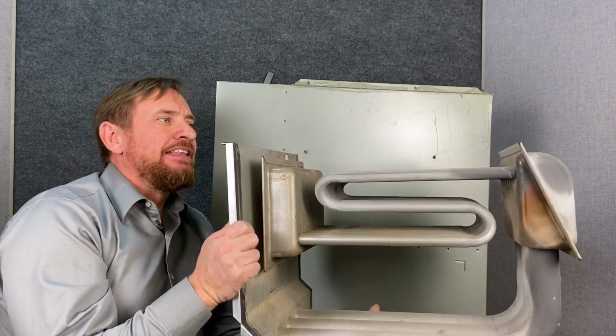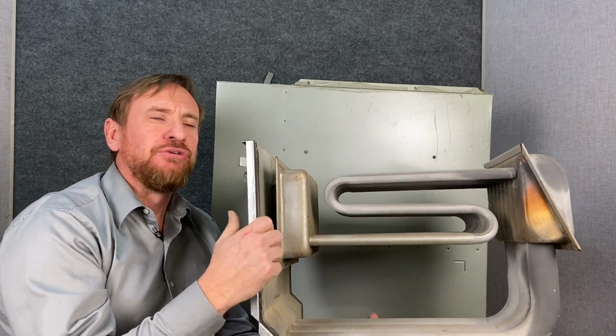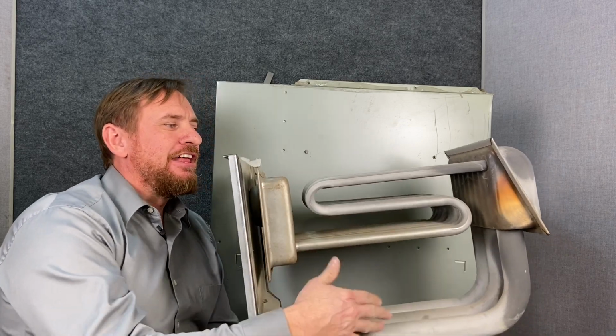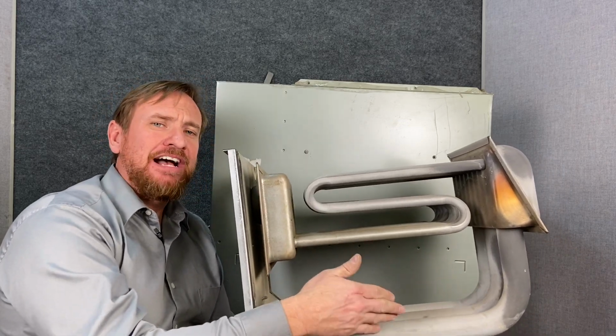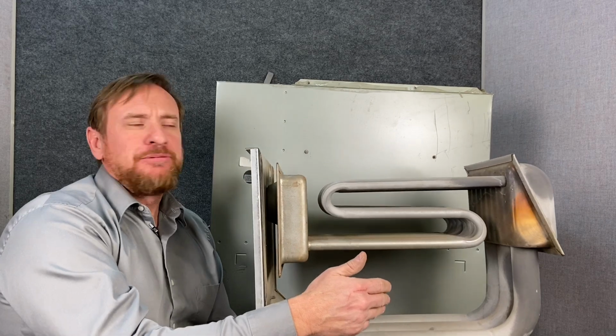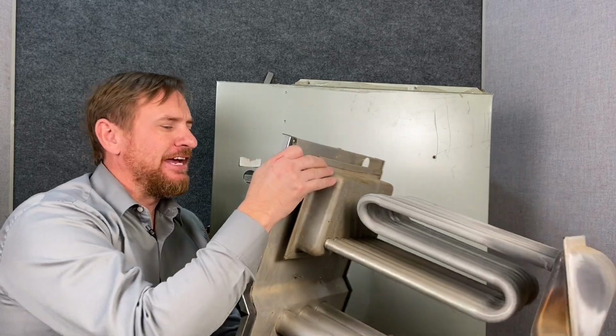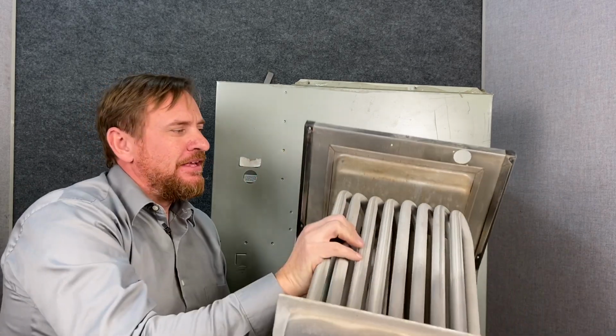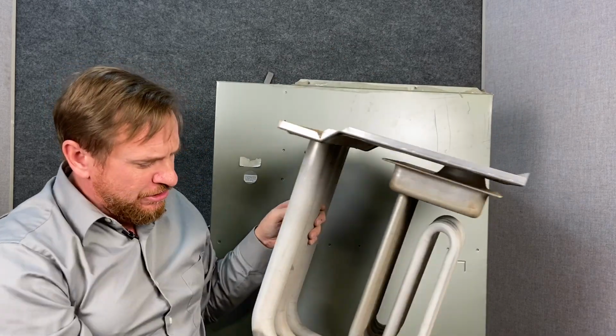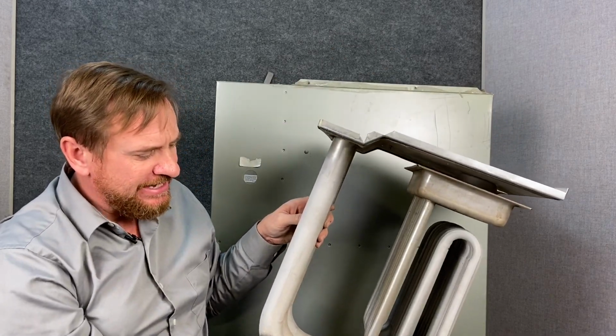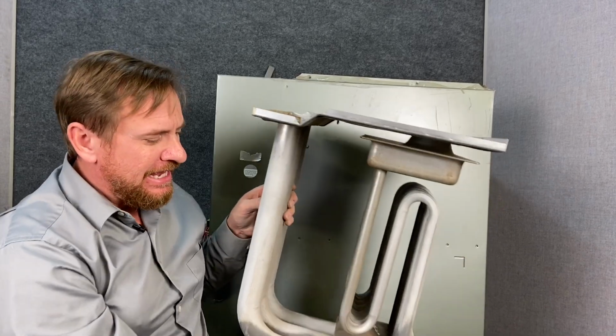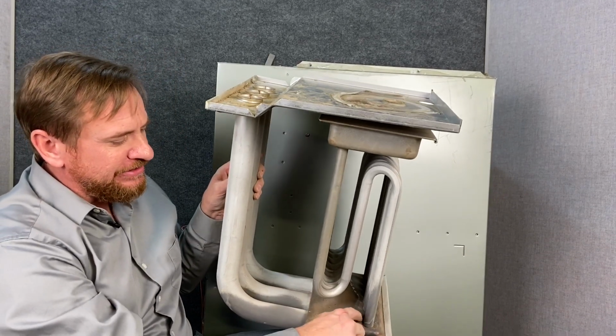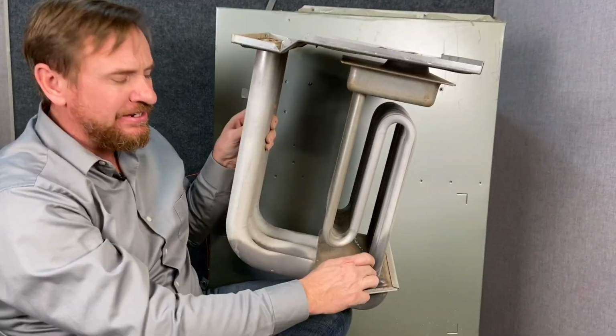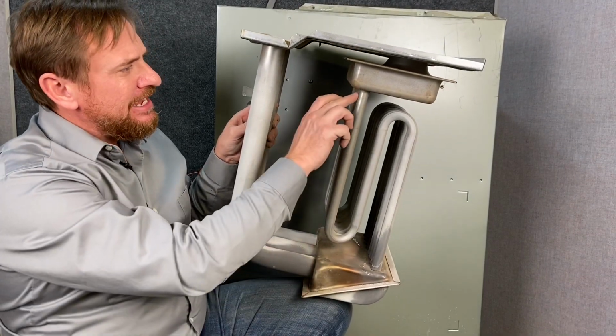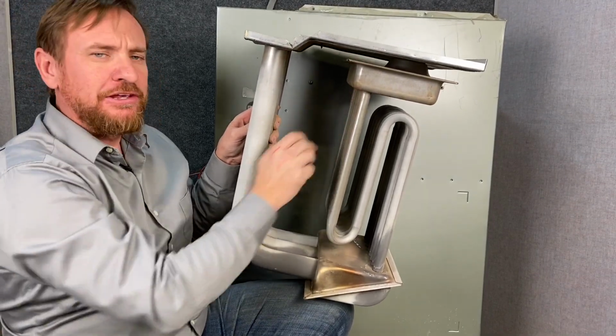Now the problem is we want to check to make sure there's no leaks in this, because if air leaks from the heat exchanger from the inside to the outside, that could cause carbon monoxide poisoning to our customers. So we want to make sure we check that. But this is our heat exchanger. And we noticed right here where this connection is, that's a notorious place for these to leak, as well as right here along these connections. Where these pipes connect together is a notorious place for them to leak. Again, right here is a notorious place for them to leak.